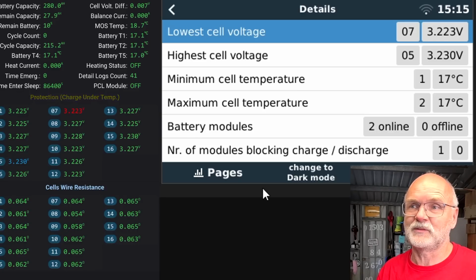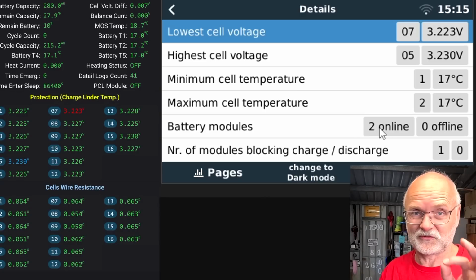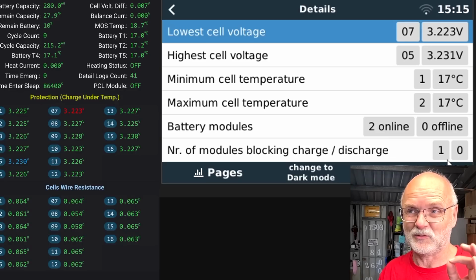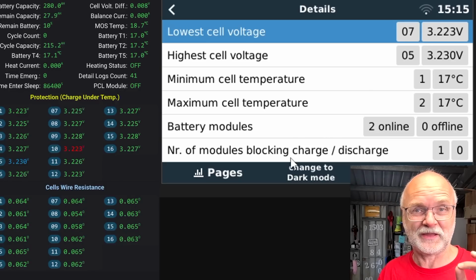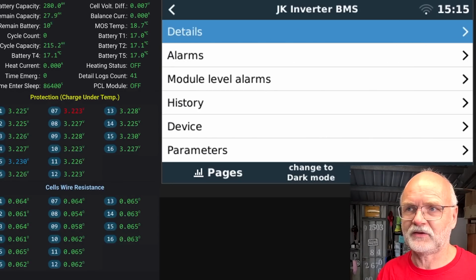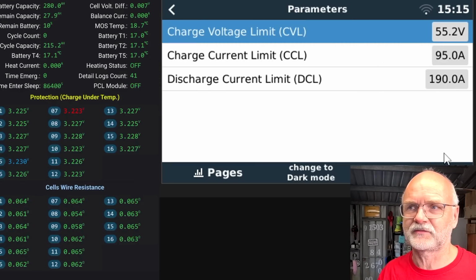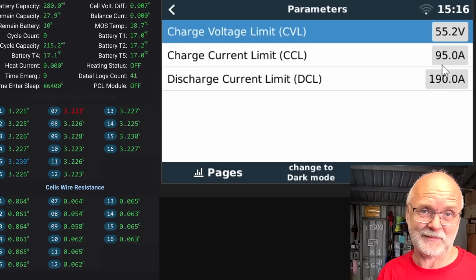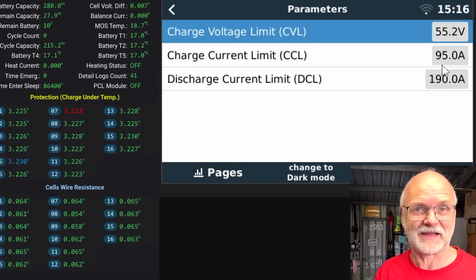And here in the Victron remote console, we can also see we've got still both batteries online, but one of them is blocking charge. And if we go back here and go into the parameters, we can also see our charge current limit, CCL, has now reduced to 95 amps only. Yeah, before it was 190.